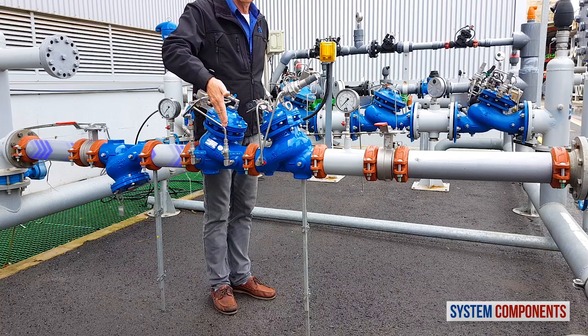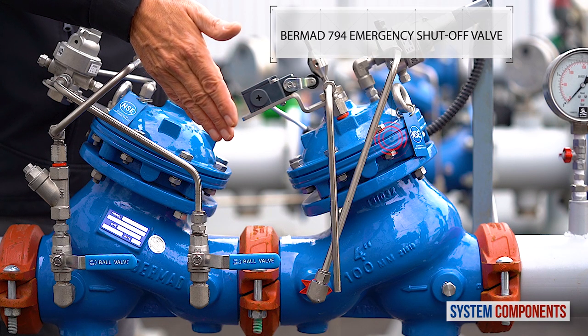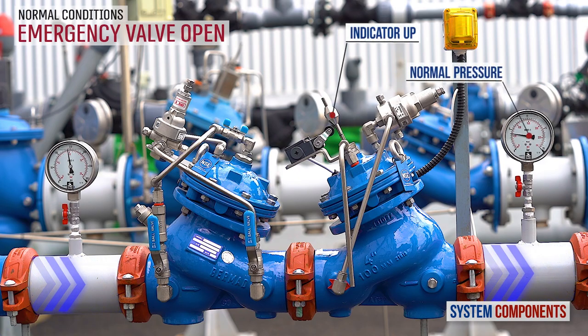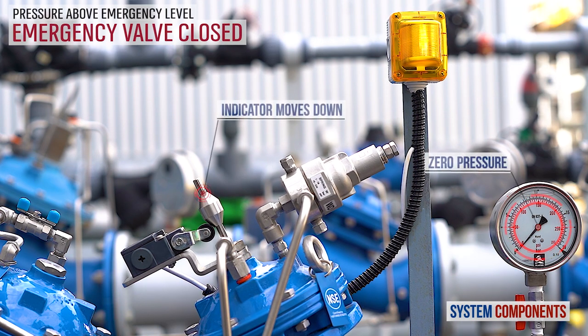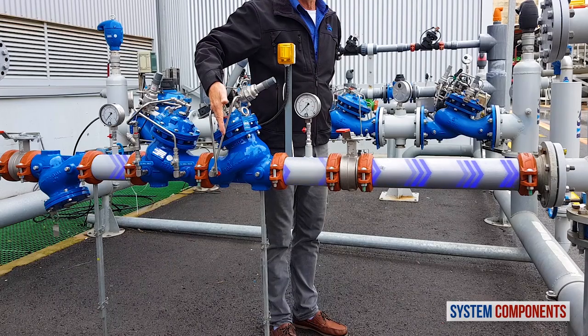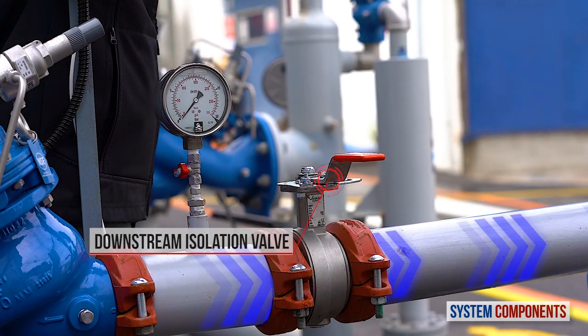The water then passes through the Bermad 794 pilot-operated emergency shut-off valve. As explained earlier, under normal conditions this valve is fully open, only entering shut-off when the consumer supply line pressure rises above its preset allowable pressure, which can be adjusted using the pilot. From here, if the downstream isolation valve is open, the water will go on to the consumer line.